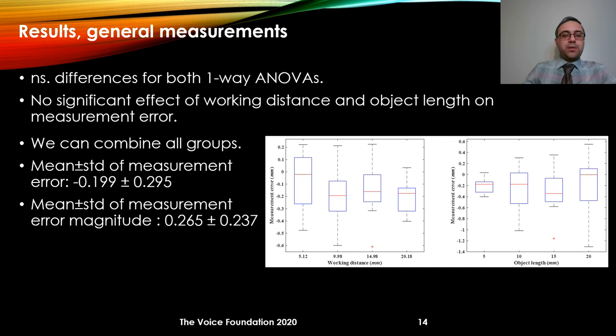Performance of the method for general measurement was evaluated using one-way ANOVA. We created four line segments with lengths of 5, 10, 15, and 20 millimeters, placed them in different spatial locations of the field of view, and varied working distances at 5, 10, 15, and 20 millimeters. Neither the effect of working distance nor the effect of object length on measurement error was significant. Combining all groups, the average value of measurement error was on the order of 0.2 millimeters.